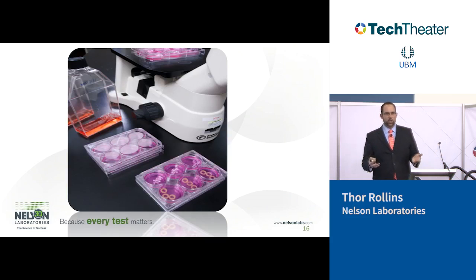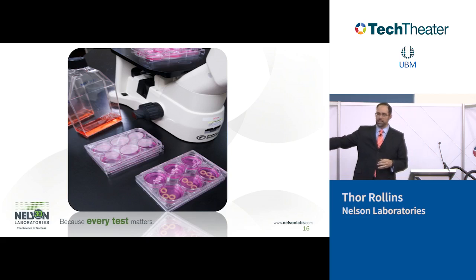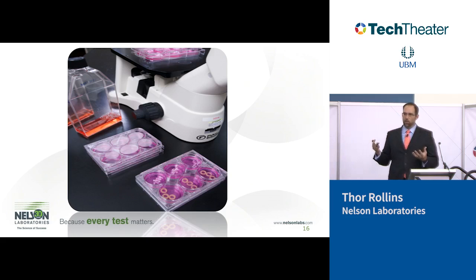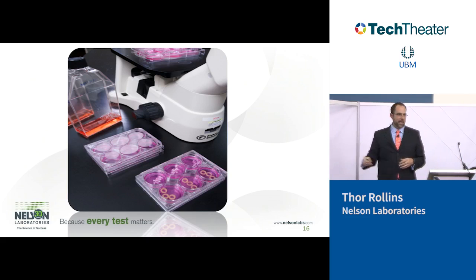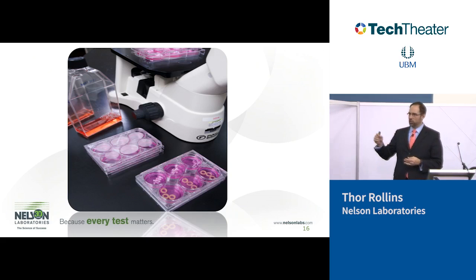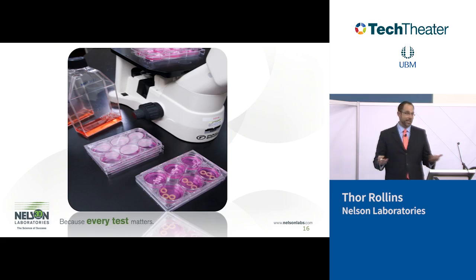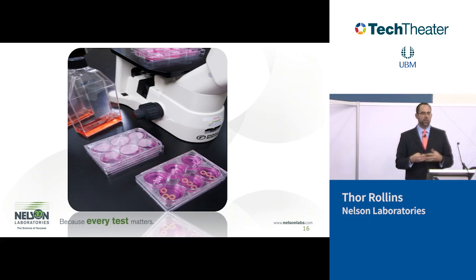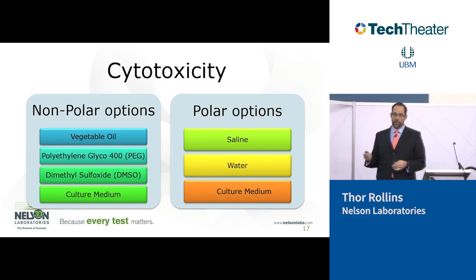Cytotox really is just evaluating the impact of your device on cells. That's what the test looks for. So we grow up cells in these flasks, and then we break these cells apart and put them in these little wells. And then we extract your device, and we put that extract onto the plates to see what happens. If there are toxic chemicals that come off your device into that solution, then they interact with the cells and kill them. And that's why it's so sensitive, because these cells are just on the bottom of the plate. There's no body system around to protect them. So that's why it's a great screening test, and it's quick and cheap.